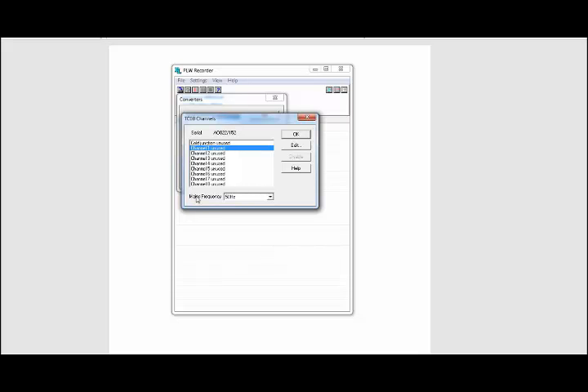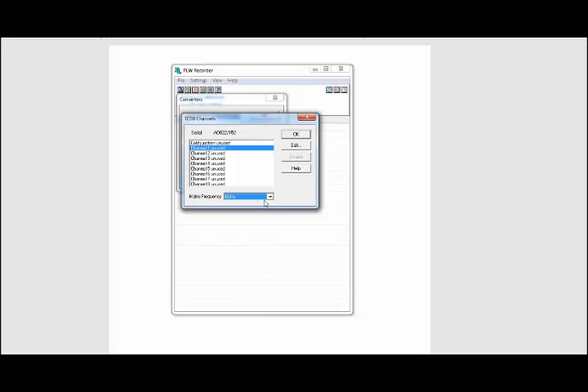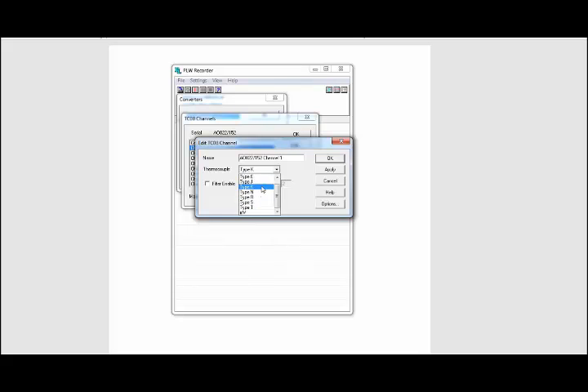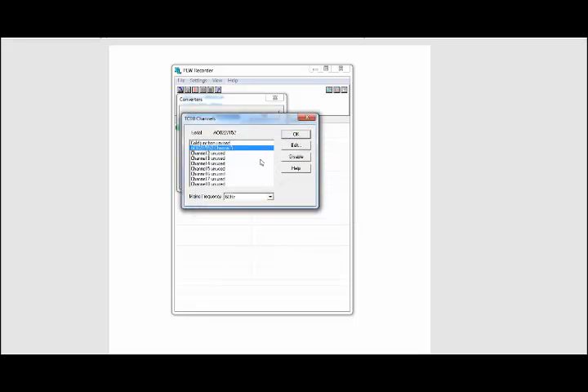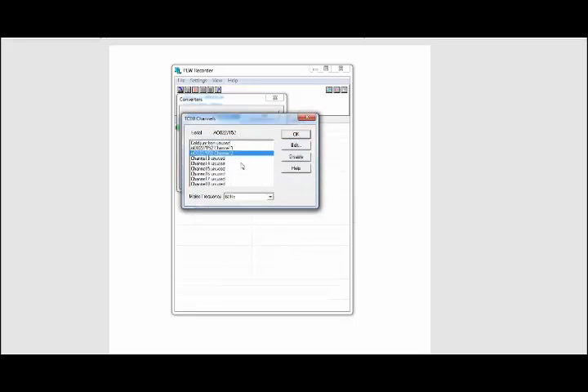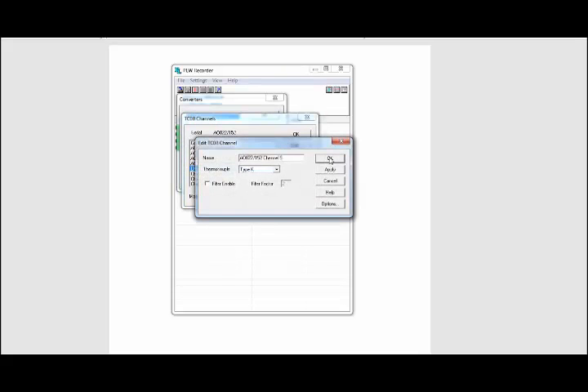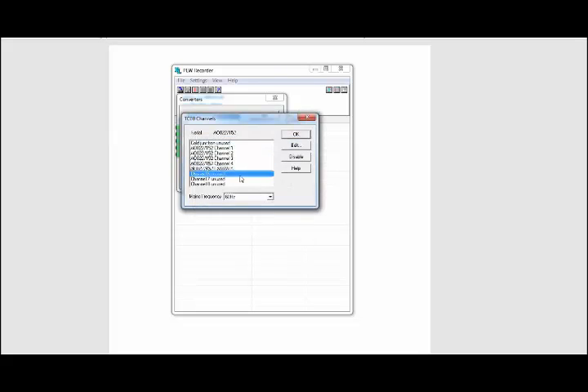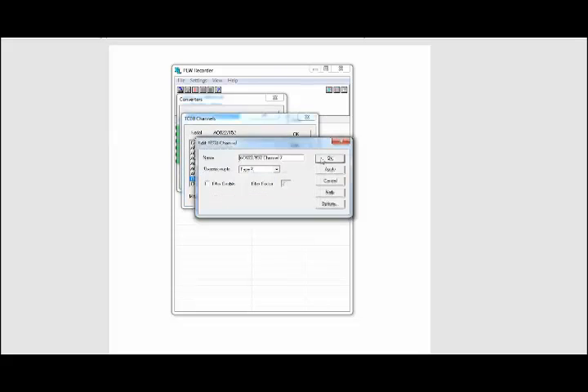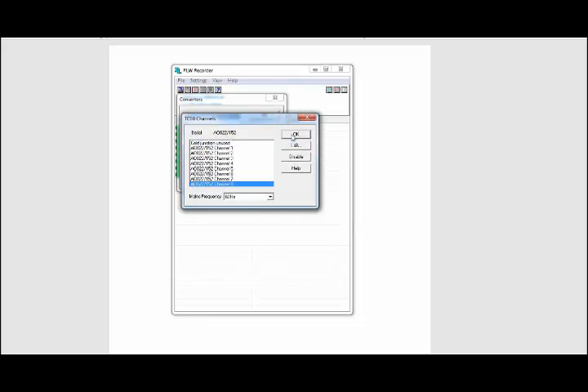The first thing you want to do is Main Frequencies. It has built-in filtering for filtering out the harmonics on our AC power lines. Europe would be using 50 Hz, here in the United States we're going to select 60 Hz. To set up the channels, just double click on Channel 1. You can change the name here if you want to and change the type of thermocouple you're using. Go through and set up all eight channels on this particular device. Hit OK when you're done with that unit.